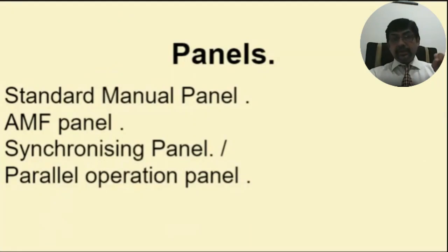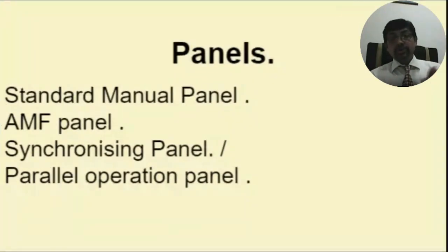An automatic mains failure panel is such that when the power is there, the load is running on power, but as the power fails, the generator will automatically start and take over the load, and the load will be intact. When the power returns, the generator will be given a command by this AMF panel to go offline, that is switch off, and gradually the load is changed over from generator to mains supply again. That is known as the auto changeover system or auto mains failure panel, the AMF panel, as the normal term in industry.